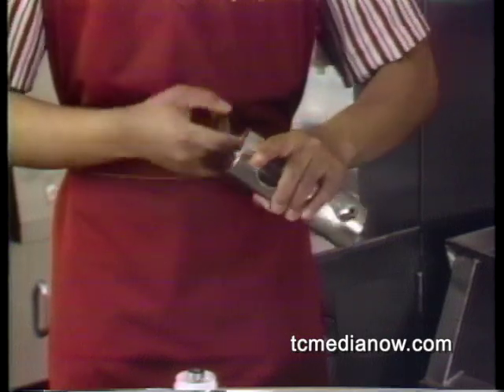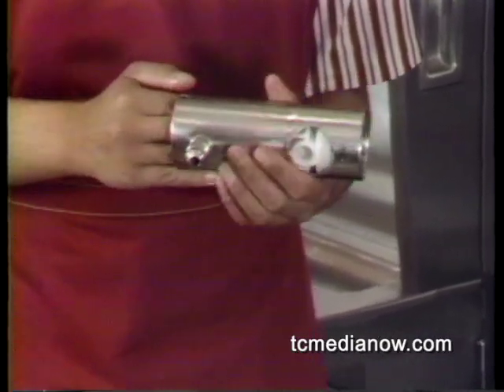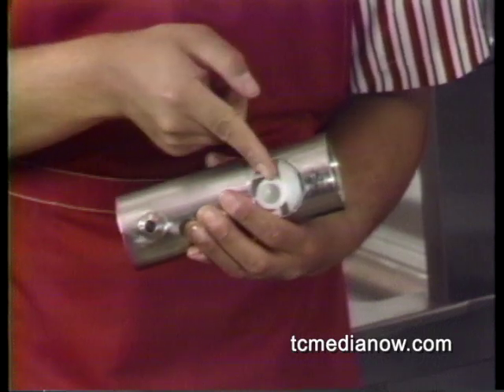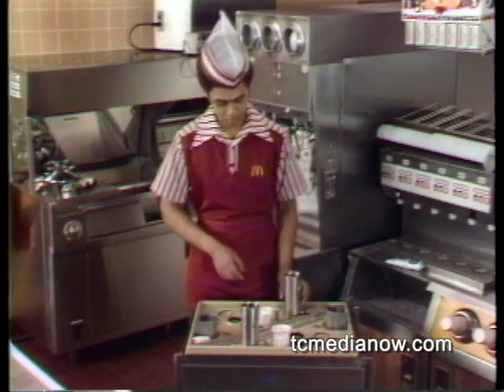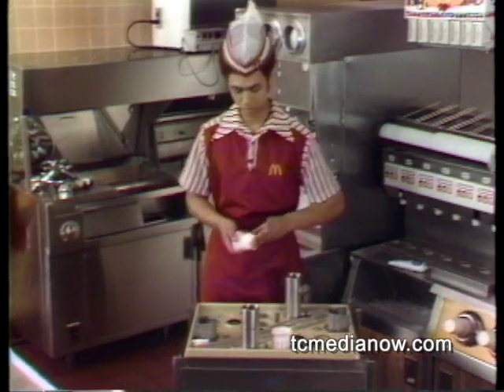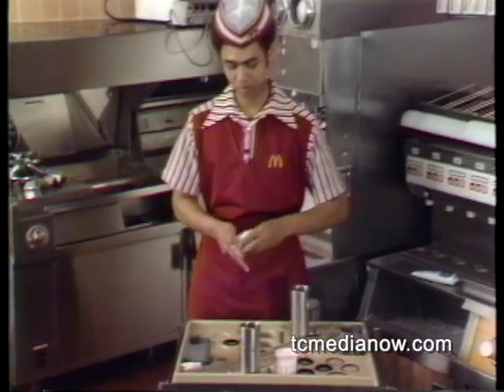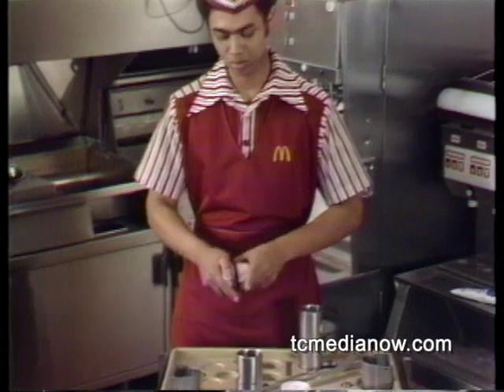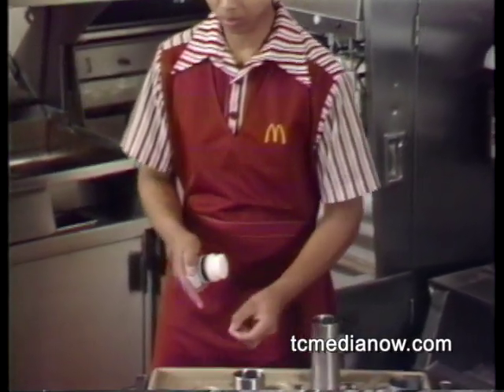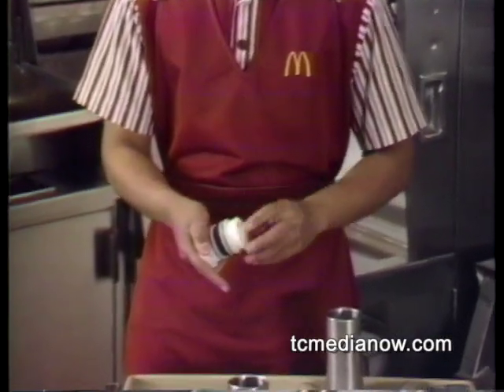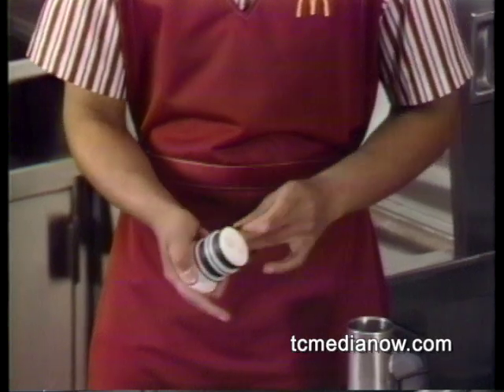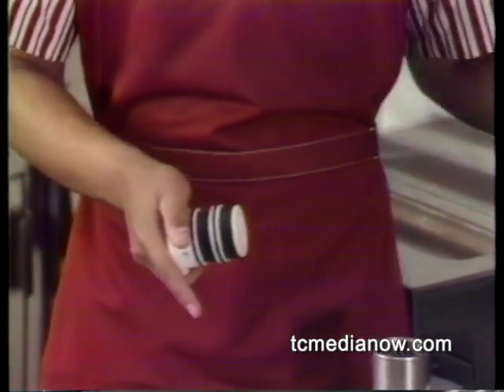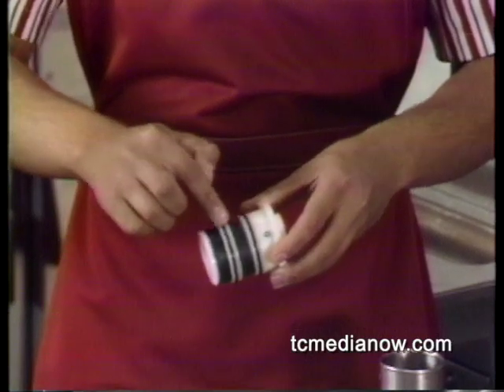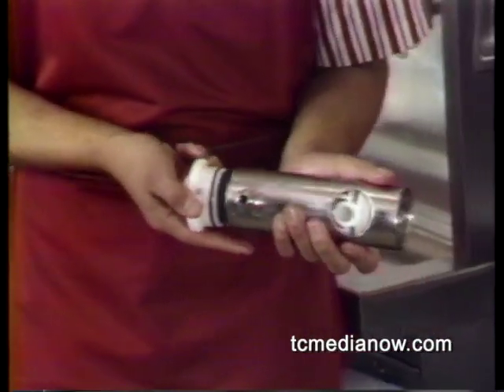After lubricating the inside of the pump housing, slip the piston into the bottom of the pump and push it all the way in. Be sure that you can see the ball check port through the large hole in the air pump housing. Now place the O-rings and check bands onto the pressure head. Remember, rough side out for the check bands. Again, lubricate only the O-rings. Next, put the pressure head into the bottom of the pump.